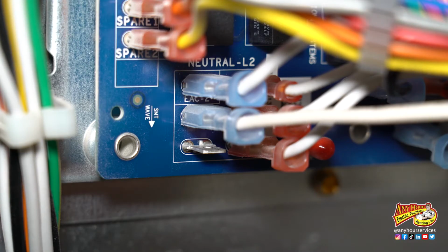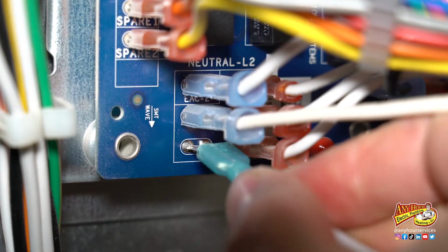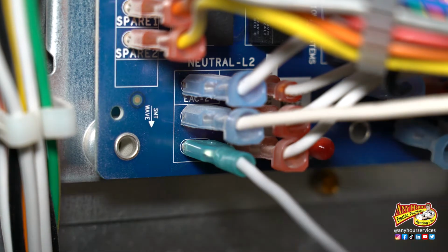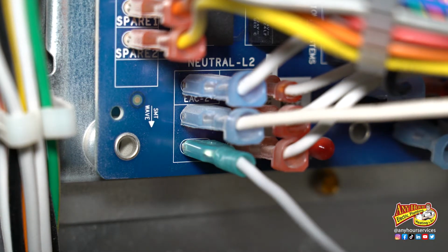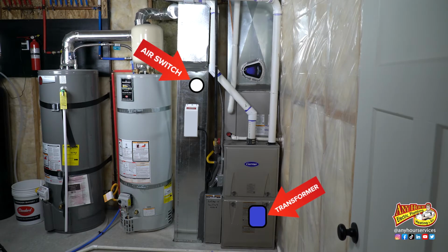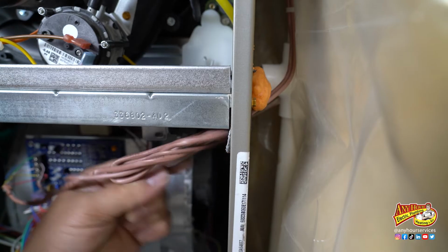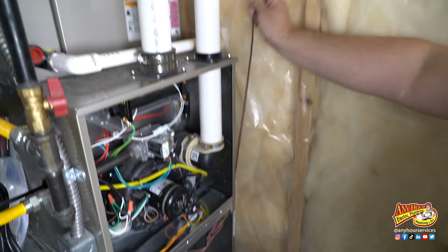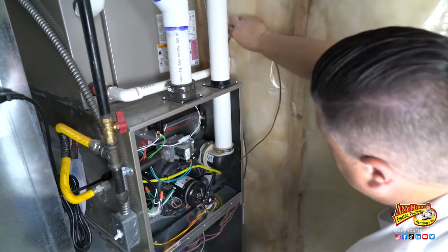Locate an open terminal on the neutral L2 section of the circuit board and plug in the white wire from the transformer there. My air switch is going to be installed further away from the transformer than the provided wires will reach, so I need to run a wire from the low voltage side of the transformer to where the air switch will be installed.